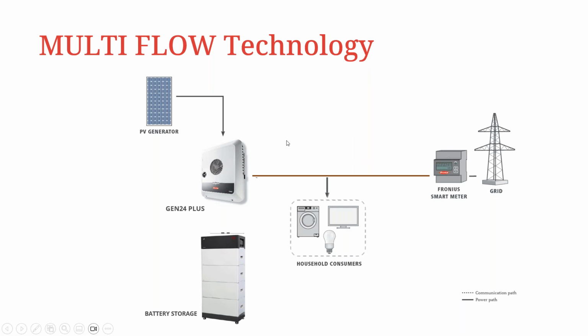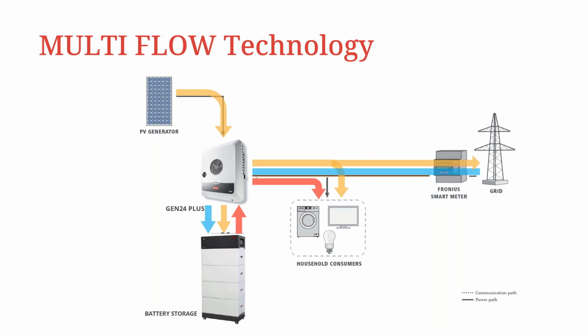So mentioning the multi-flow technology. So this is when you have your PV generation that is then fed directly through to your inverter, which is then helping to supply the loads. And if additional energy is there, you can then feed back directly into the grid, as well as doing your battery charging at the same time. You can also pull directly from the battery storage to help feed additional loads if the loads are too great for your PV generation to compensate for, as well as also using your grid supply to help recharge the battery during discharge. You can then also have an AC coupled solution, which is where you're using an additional PV generator to help feed loads back in or to help recharge the battery.